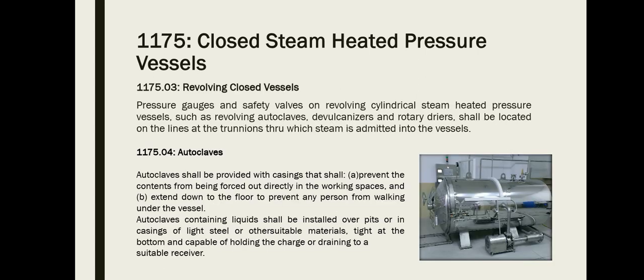So next is the revolving closed vessels, Rule 1175.03. Pressure gauges and safety valves on revolving cylindrical steam heated pressure vessels such as revolving autoclaves, devulcanizers, and rotary dryers shall be located on the lines at the trunnions through which steam is admitted in the vessels. So dapat nakalocate siya sa steam nga admitted sa vessels.